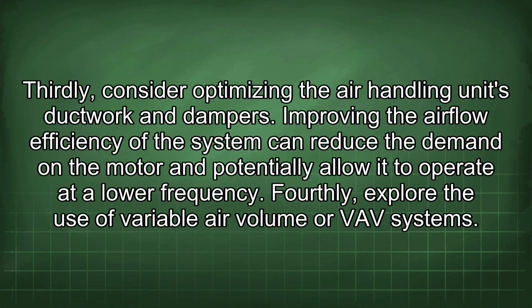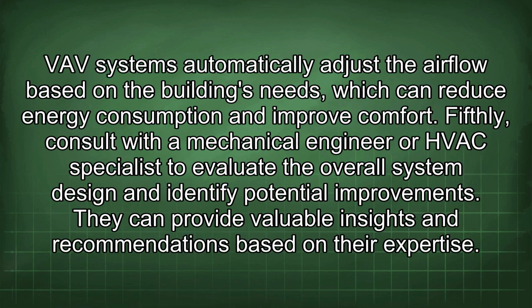Thirdly, consider optimizing the air handling unit's ductwork and dampers. Improving the airflow efficiency of the system can reduce the demand on the motor and potentially allow it to operate at a lower frequency. Fourthly, explore the use of variable air volume or VAV systems. VAV systems automatically adjust the airflow based on the building's needs, which can reduce energy consumption and improve comfort. Fifthly, consult with a mechanical engineer or HVAC specialist to evaluate the overall system design and identify potential improvements. They can provide valuable insights and recommendations based on their expertise.